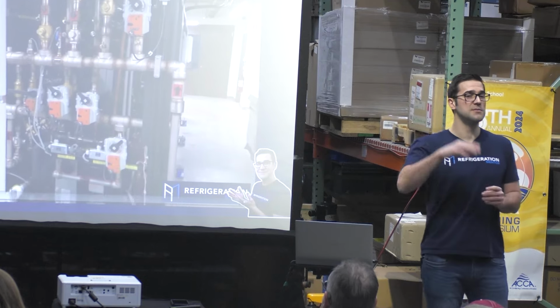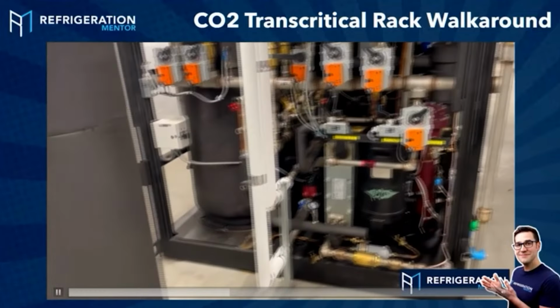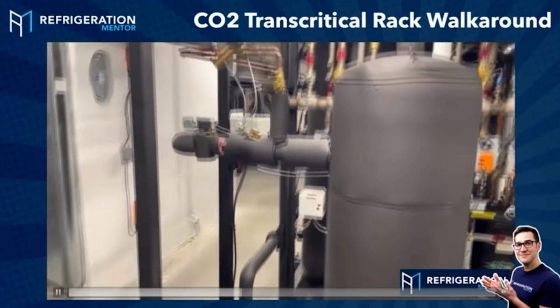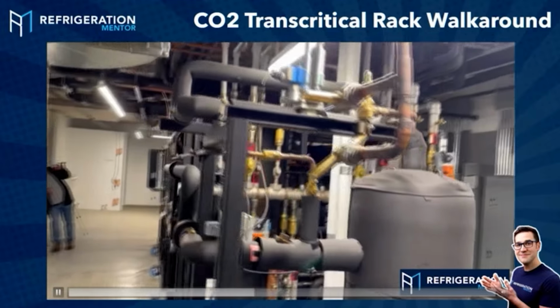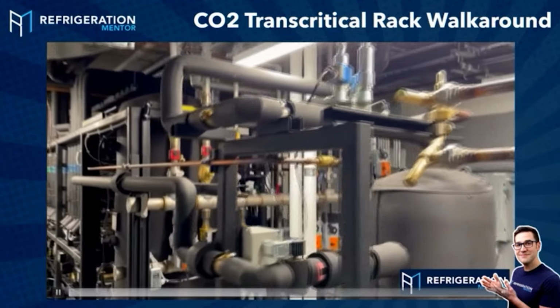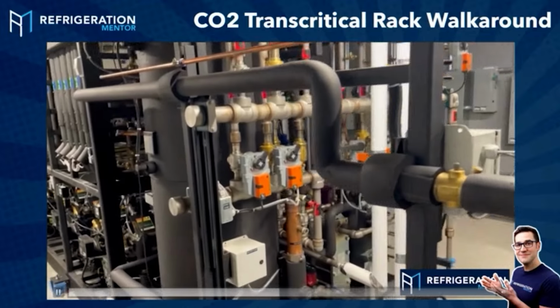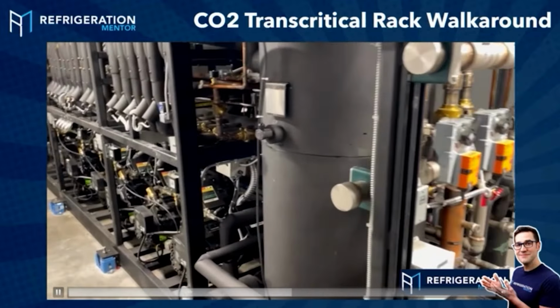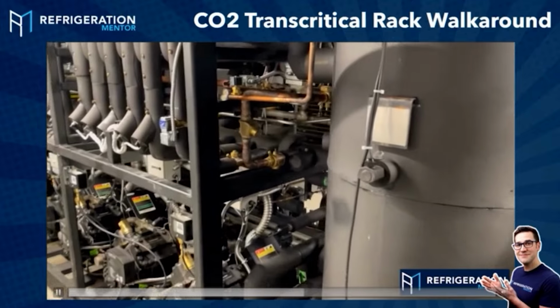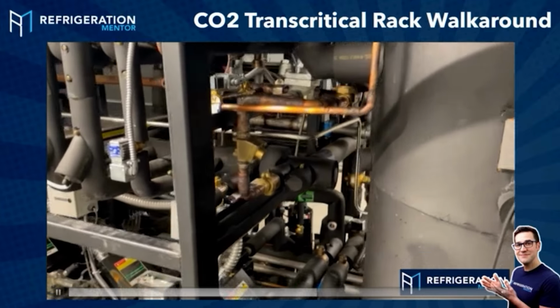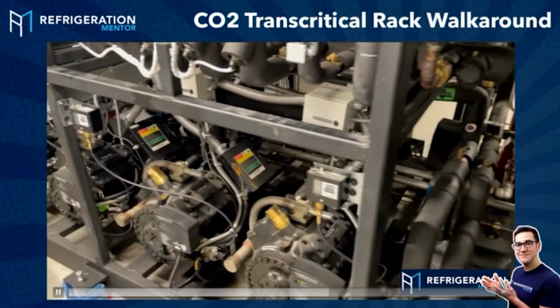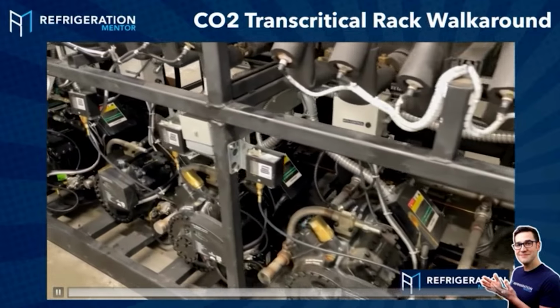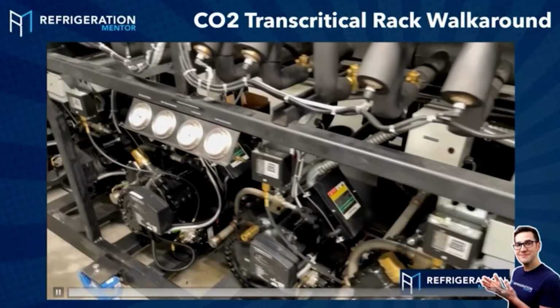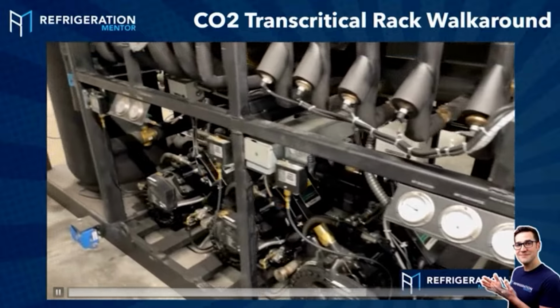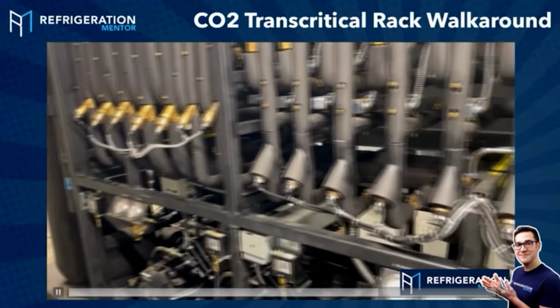Here is a bunch of Belimos. How many of you work on zoning systems? Show of hands. So almost all of you. That's zoning. So think about the zoning that you do in an air conditioning or HVAC system. That's zoning on a refrigeration system where we're moving the heat to different parts. Then we have our receiver right here. This is the receiver that stores all that liquid refrigerant. And then as we go through, these are the medium temp compressors. So if you work in refrigeration, there are semi-hermetic compressors. And then at the end is the air conditioning circuits.